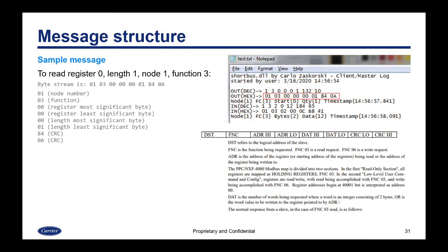Here is a sample message structure. If you wanted to read register 0 for a length of 1 from node 1 using Function 3, you would create a byte stream as such. Normally this will be abstracted by your software or PLC — you just specify which register to read, how many registers, the node address, and the function code, and the byte stream is created for you. The stream starts with a node number, includes the function, has two bytes for the starting register, two bytes for the length, and then creates a CRC to error-check the message on the other end.